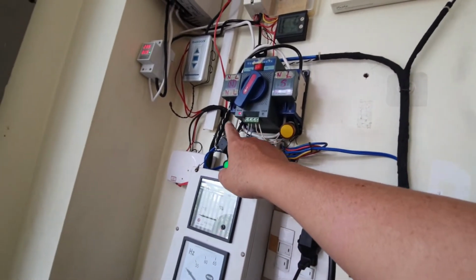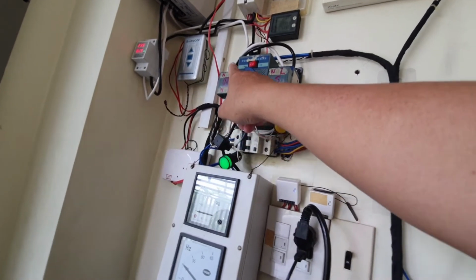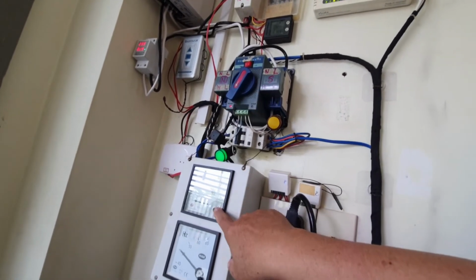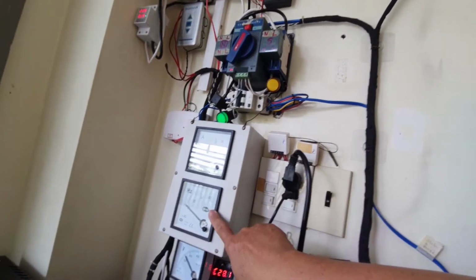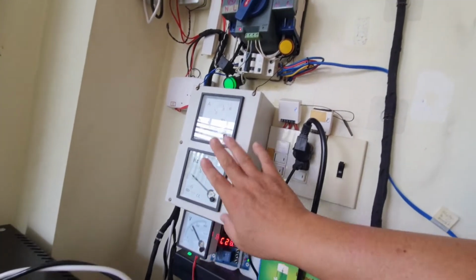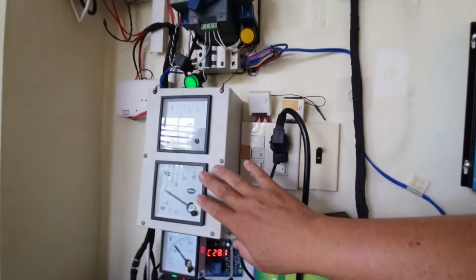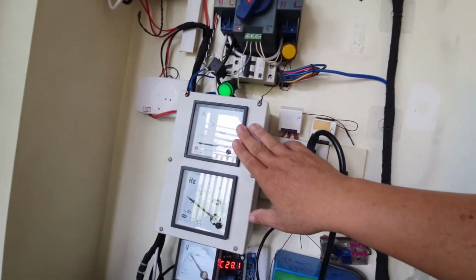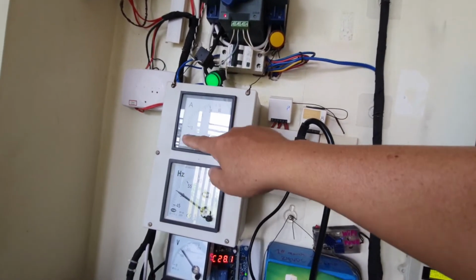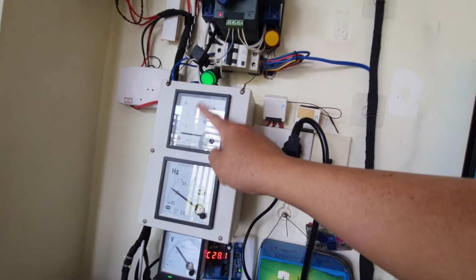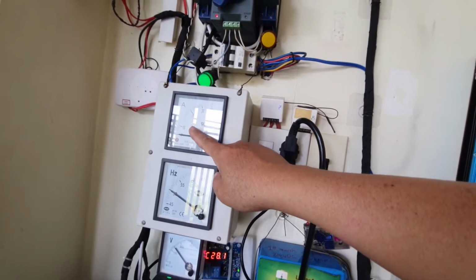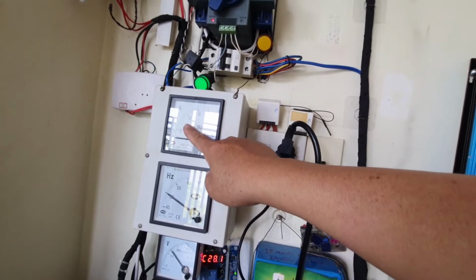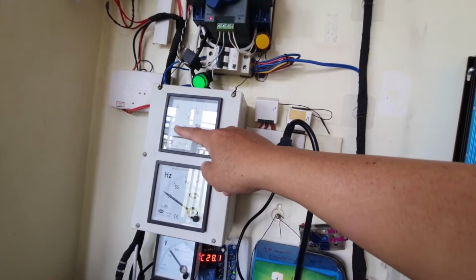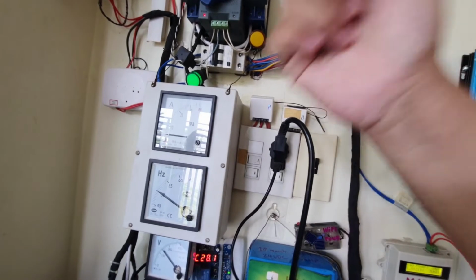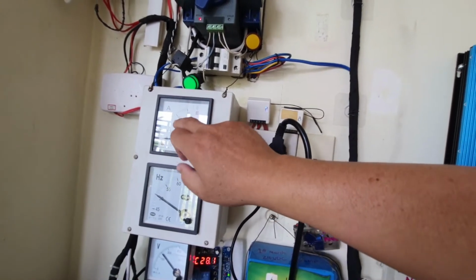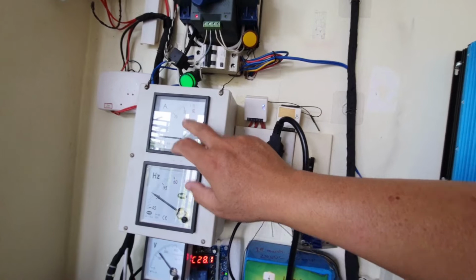So the normal power, the normal supply, comes into the ammeter, hertz, and voltmeter. Hertz, of course, is important. The ammeter is for me to see my compressors, air cons, and all that, how they function, any jumping or too much draw. If I see something consuming too much power, too much amps, that means the compressor needs to be serviced or something. This way I can sense it out.